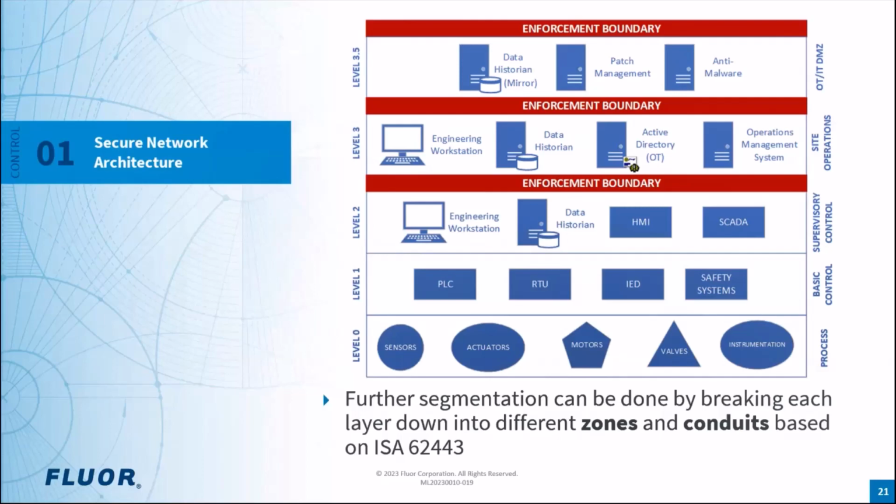So the idea is, in general, that network segmentation is an iterative process that we just continue to go through until we've broken down the entire network into its simplest collection of systems, right? Logically grouping them together so we can apply those protections to control the flow of traffic, right? Through things like access control lists and firewalls. So we can tightly control this communication, and ensure that the plant has the communication it needs to stay up and running, uninterrupted, but that if an attacker is able to get on the network, or if it's a piece of malware, we significantly reduce the cyber risk that they present to the environment.